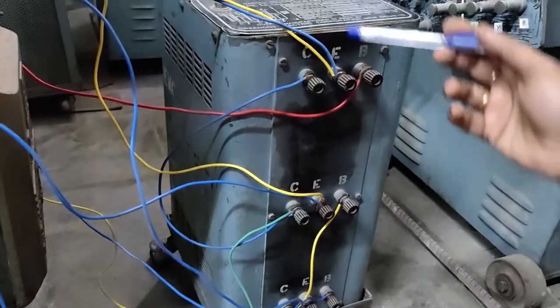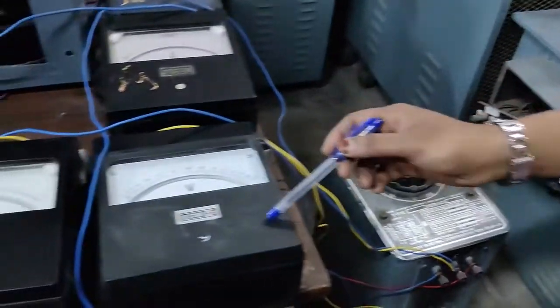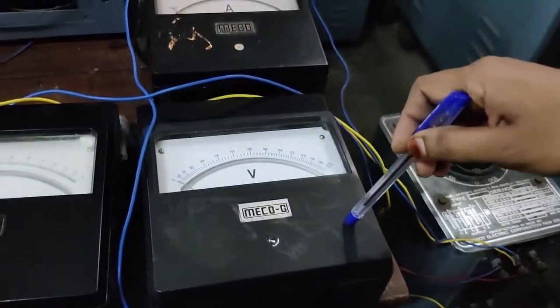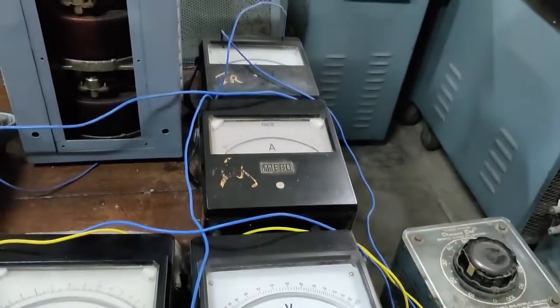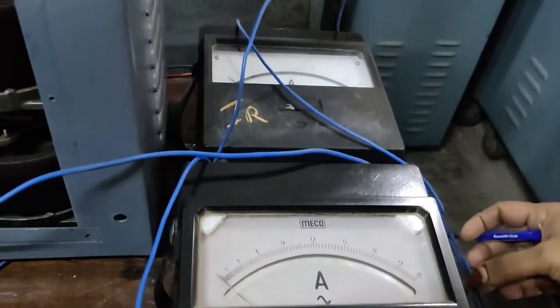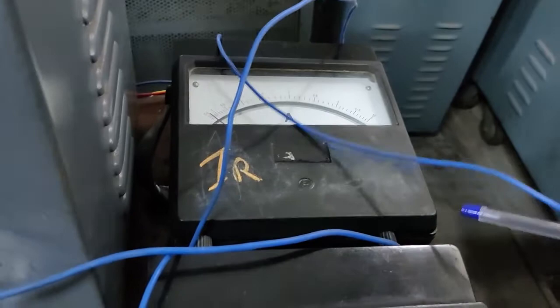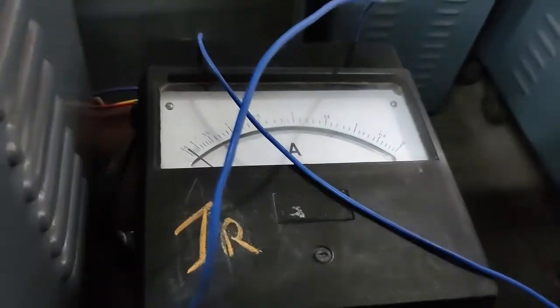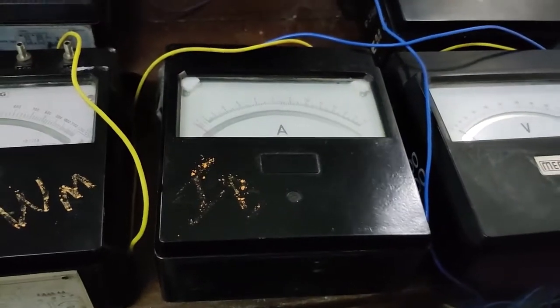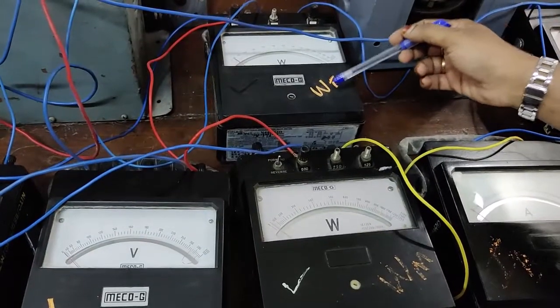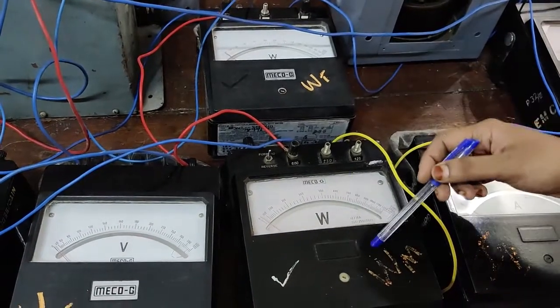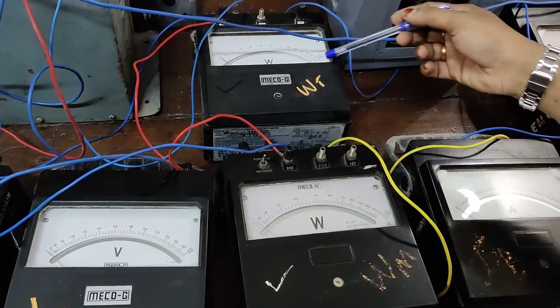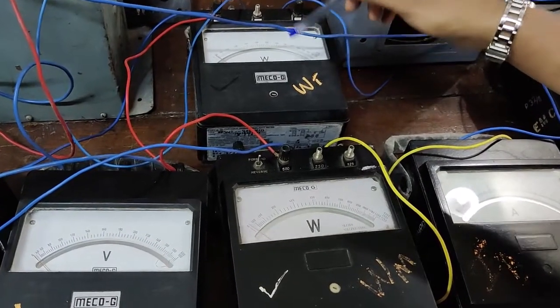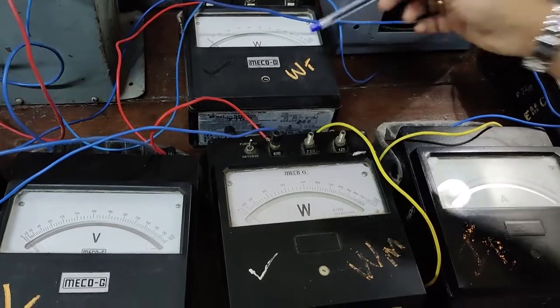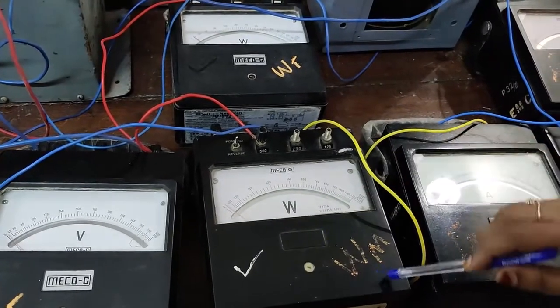And then we have this voltmeter for measuring the rated voltage from the supply, and as per the circuit diagram we have three ammeters for measuring the phase currents IR, IY and IB. And for the power measurement using 2 wattmeter method, we have 2 wattmeters. In teaser transformer side it is WT, and in main transformer side it is WM.